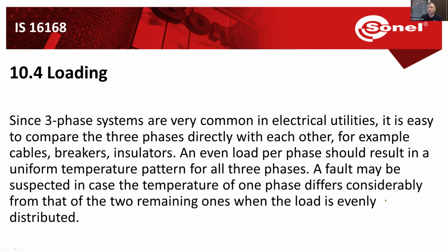Next, loading. We want to make sure the electrical objects we're checking are live, energized, and under some load, which creates a current flow. As current flows, some objects heat up, overheat, and so on. We also need to evaluate if the load is even across all three phases, so we can compare them with each other.